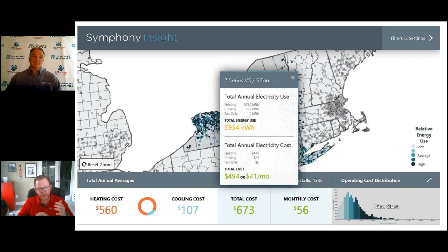Are there ground source heat pumps that don't work as efficiently or effectively? Absolutely. Does it have very much to do with the ground source heat pump equipment? No. Does it have a fair bit to do with the application, design, and installation? Oh yeah. So it comes back to making sure that as stakeholders get involved and draw the line in the sand, like Enbridge saying here's a program we're going to run and here are the stipulations, we want those stipulations to result in comfort for the end user and satisfaction for the whole industry.